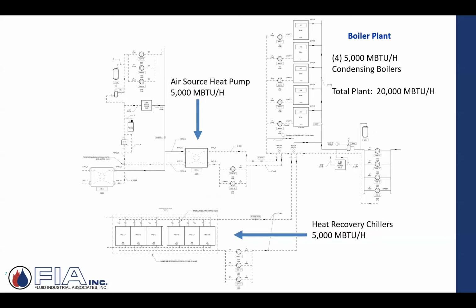One last drawing here, I just want to show as an example is this is becoming commonplace now. Maybe air source heat pumps, maybe heat recovery chillers, and then maybe my condensing traditional gas-fired boiler plant. And I might be acknowledging or trying to participate in that electrification or decarbonization that's taking place in the design world. And so maybe based on loads and outdoor air temperatures, system conditions, I might have the ability to never turn this boiler plant on for certain periods of the year. And I might be using my air source and or my heat recovery chillers. How do I connect all of that technology, all that pumping, and have it all work properly within this system?